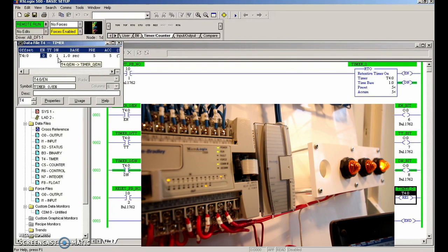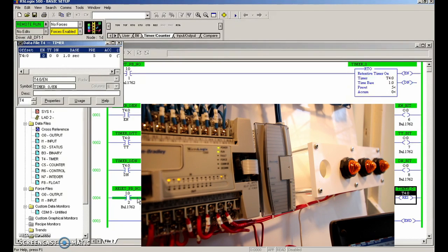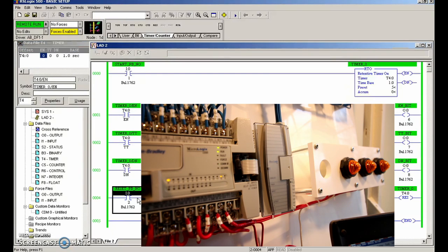and the only way to change that is by placing a reset input. I'm using a push button, could be anything that you're using. There is an input there in order to reset your timer. So I'm pressing it now, and it goes down to 0. All right, guys, that's pretty good. That covers our on delay timer, or the TON, the off delay timer, which is the TOF, and then finally the retentive on delay timer for our RS Logix 500.